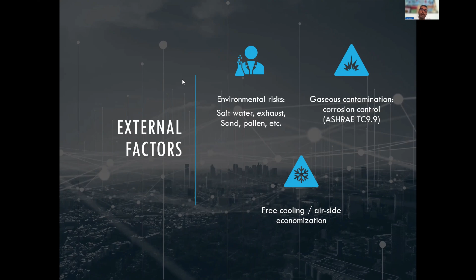OEM factors. I'm a big believer in always involving the OEM, the original equipment manufacturer, in the decision when we're talking about what type of filters. Oftentimes, they will make recommendations on the types of filters, and more often than not, the facility managers will start with those recommendations for the first change, two changes or so. After a while, we look to improve on them, but not forgetting about what the original recommendation was, because that takes into account flow rates, CFM, sizing, and all different number of things. So we're going to go through a few examples of some popular types of equipment. The actual manufacturer really isn't as important as the type of equipment is.